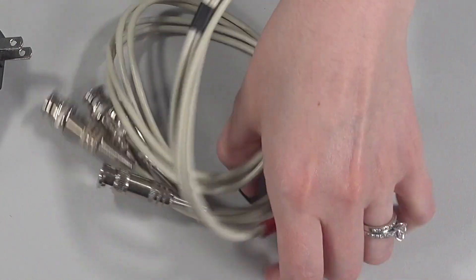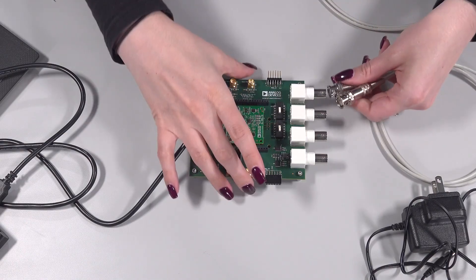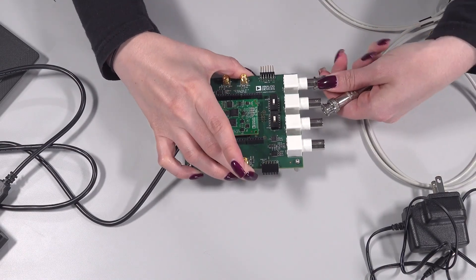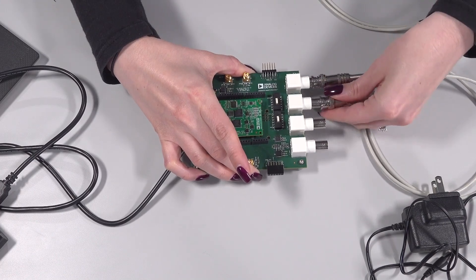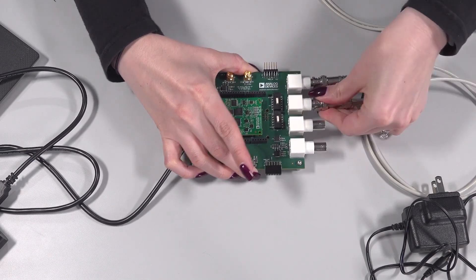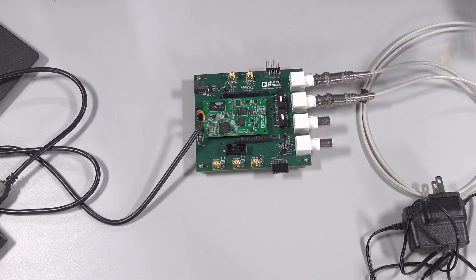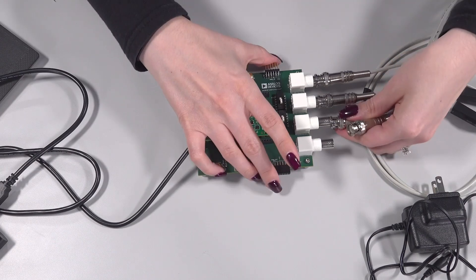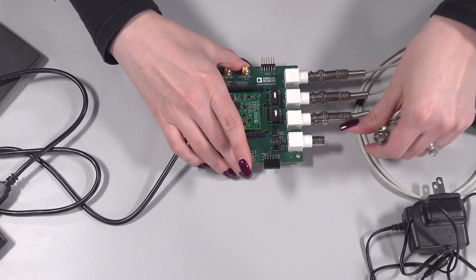Test leads are color-coded, ensuring proper connection to your testing components. Connect the BNC cables from the red clips to the H-cur and H-pot connectors and connect the BNC cables from the black clips to the L-cur and L-pot connectors.